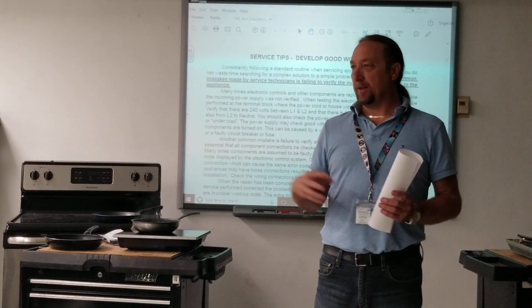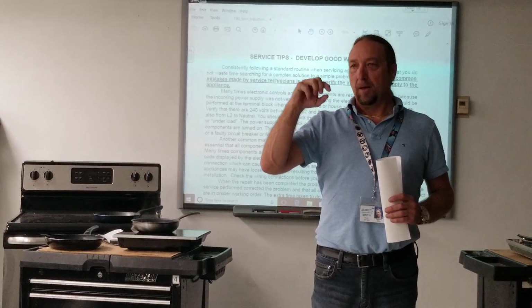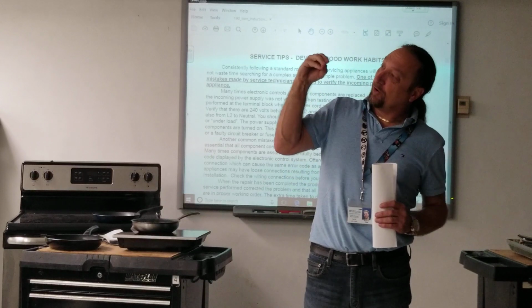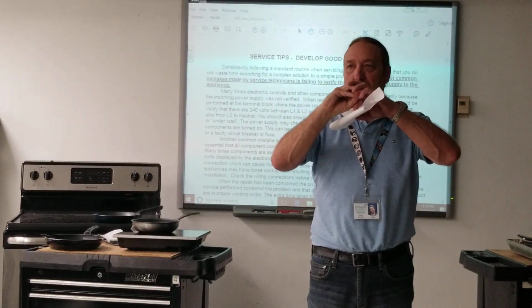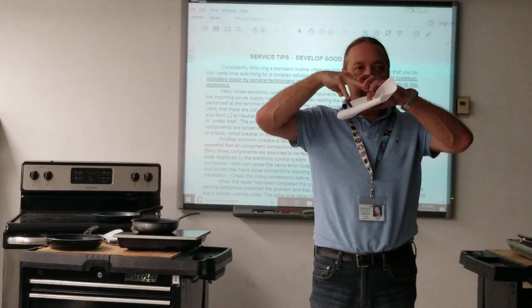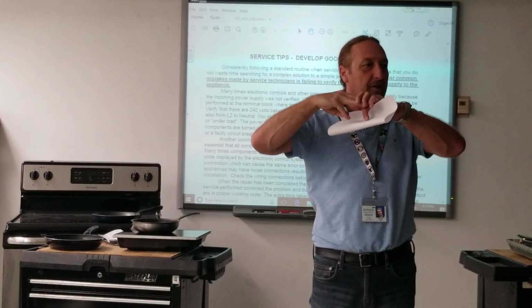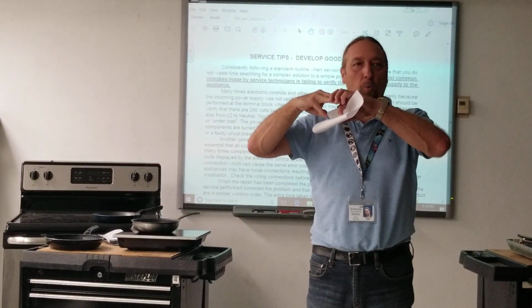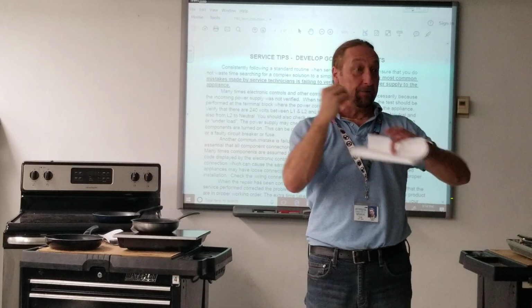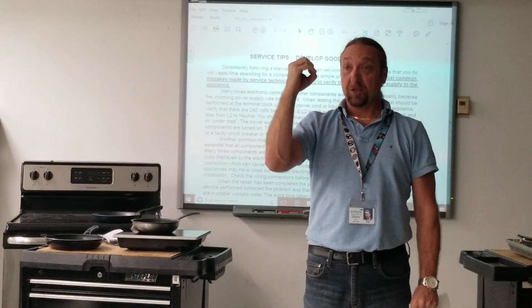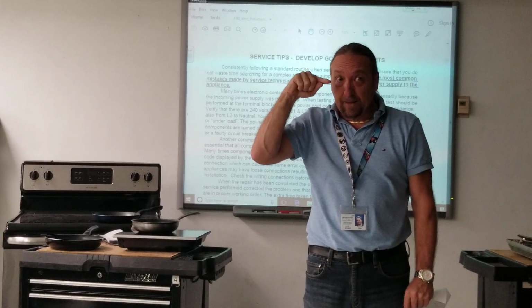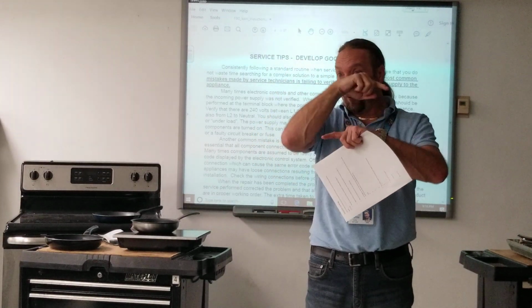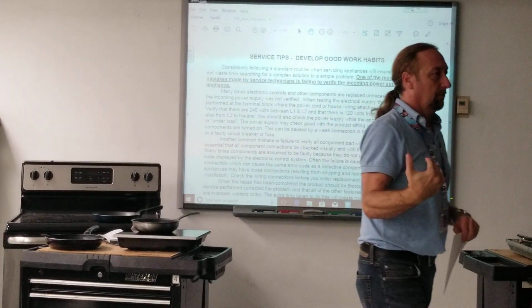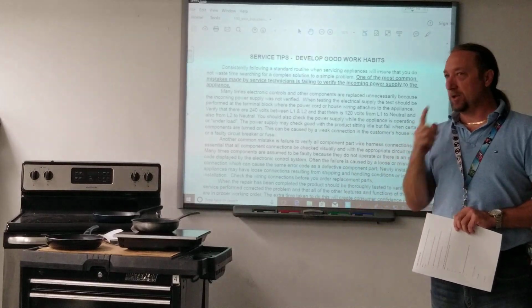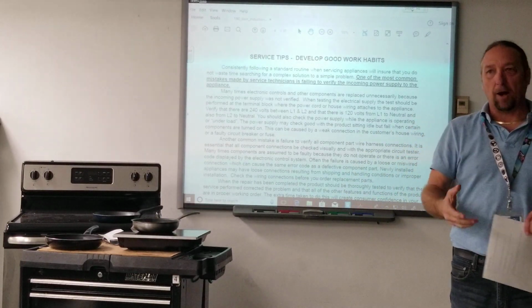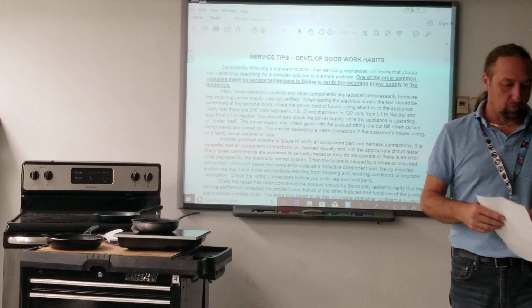An example of that would be the wires connected into the outlet in the wall. Most wire is stranded, like 30 or 40 strands of copper wire, and then a screw screws down. Sometimes they don't catch all the strands, so you only get 2 or 3 strands and the rest aren't in there. If you check voltage, it'll read 200 volts. But like a water hose, the hose may be this big and when water's coming out of it, it shoots at that thickness. But if you're coming out of a smaller opening, you won't get the full amount of water flowing out. So as soon as the appliance comes on, the voltage drops. It could be burnt, or it could just be poor connections. So you want to check it under load, but also make sure the wiring, the circuit breaker, and everything else is in good condition.